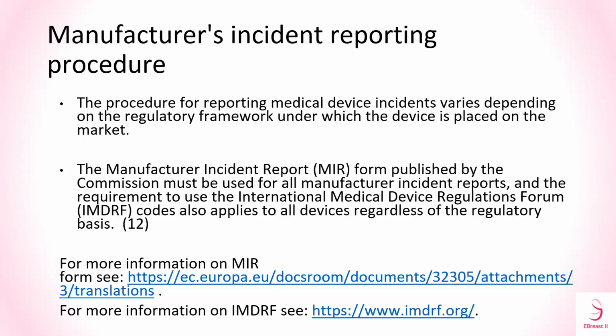The procedure for reporting medical device incidents varies depending on the regulatory framework under which the device is placed on the market. The Manufacturer Incident Report form published by the Commission must be used for all manufacturer incident reports, and the requirement to use the International Medical Device Regulators Forum codes also applies to all devices regardless of the regulatory basis.